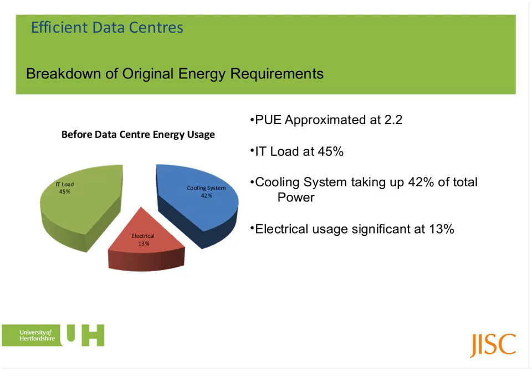A ratio, so if the PUE was 2, then for every kilowatt that went to your IT equipment, a kilowatt would be used on the facility as well. We were about 2.2, and that was after we'd moved all of our racks and equipment out into a temporary data center, so it probably understates where we really were at, because it was pretty appalling before. As you can see, the IT load itself only took 45% of the total power that went into the facility, because a massive 42% was going to just cool the room and the servers.